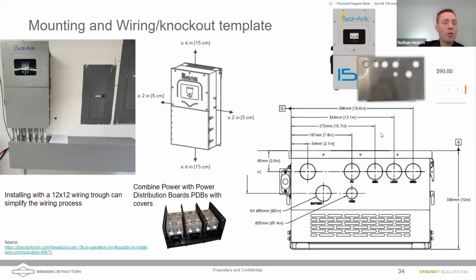I recommend installing these inverters with wireways. So I'm showing you an example here. This is a 12 by 12 wireway. So there's a fairly large depth to this inverter compared to some of the others on the market. The inverter's footprint is typical, but the depth is a bit bigger. So with a 12 by 12 wireway, it makes it fairly easy to make the knockouts in the bottom of the inverter match up to the wireway.